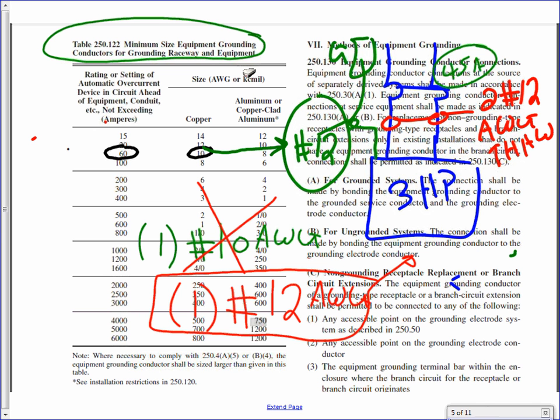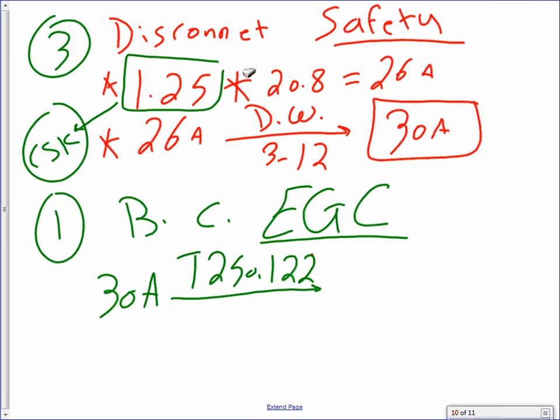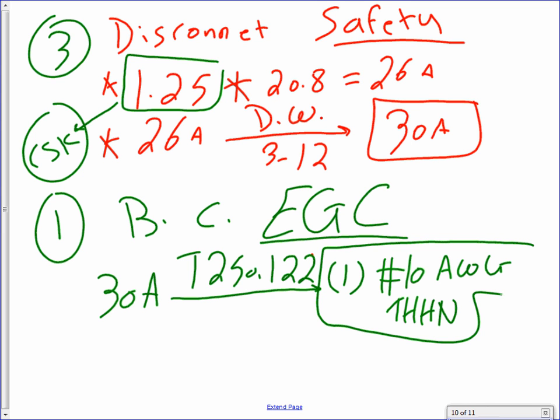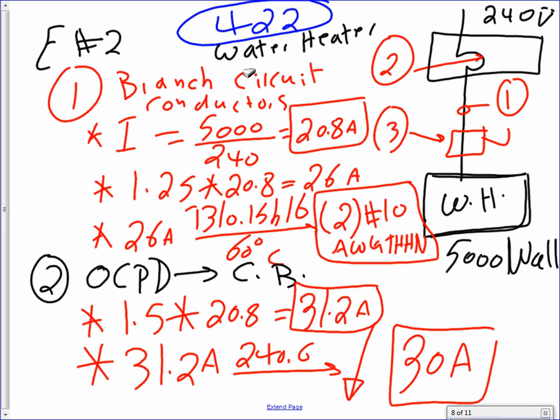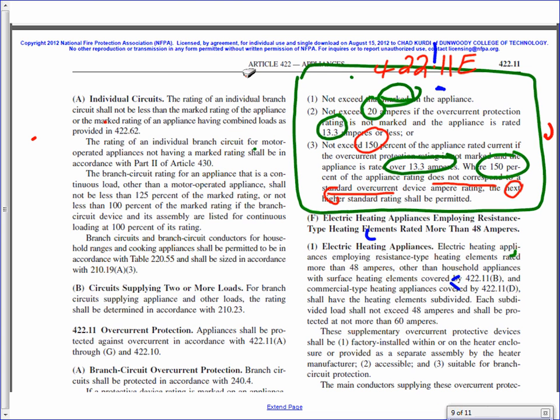So for 30 amps, what do you need? Number 10, right? Can you guys see that? Yeah, for 30 amps, we need number 10. Then my equipment grounding conductor is going to be one conductor, number 10 AWG THHN. Do I have to lower that number 10 to number 12? Why not? Because the phase conductors, the hot conductors, are number 10. Had they been number 12, then you would lower it to number 12.